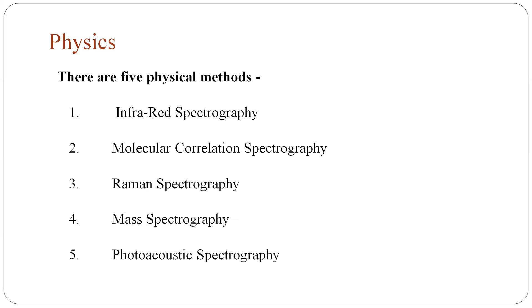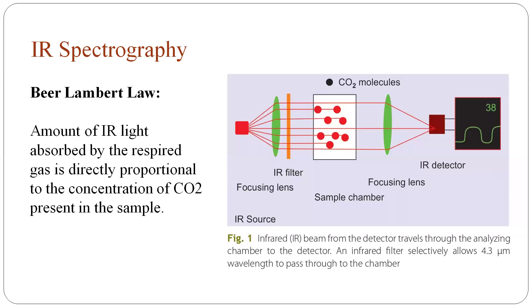Here, if you see, this is the infrared light source, and through this infrared light will be passed, and this is the infrared filter which filters 4.3 micrometer infrared light to pass through, and it is then passed through the CO2 chamber containing CO2 molecules. The infrared light will be absorbed by the CO2 molecules present in this chamber. The remaining unabsorbed light will be passed through this chamber, and it will be detected by the infrared detector, which then shows the EtCO2 level.